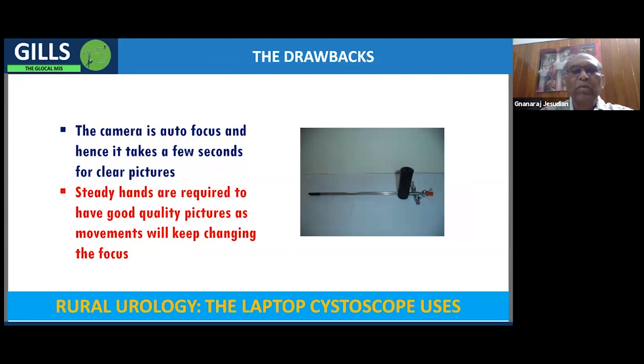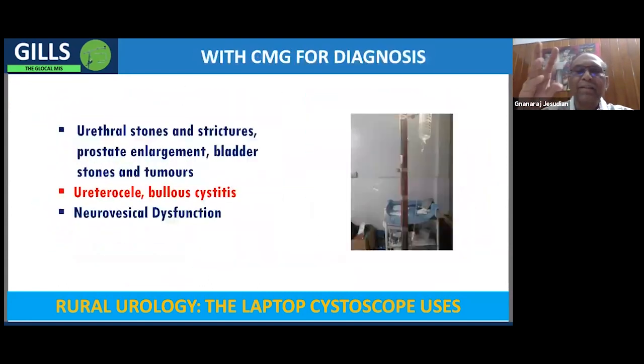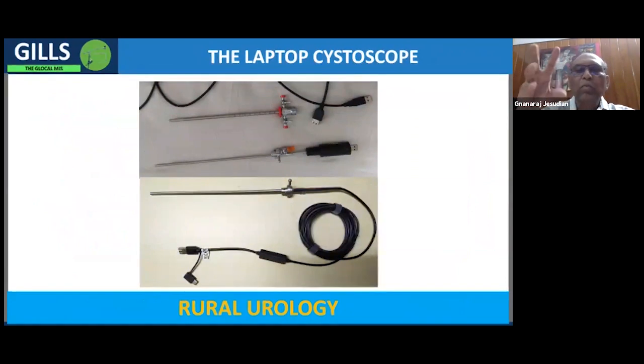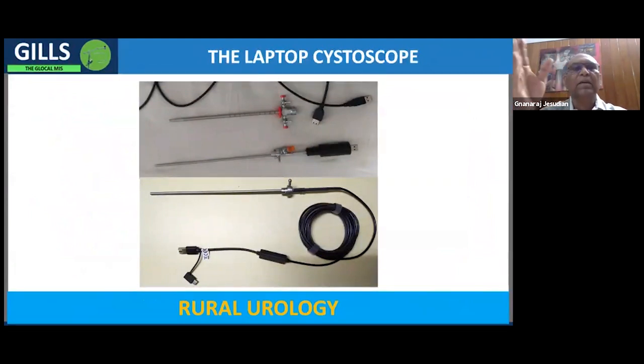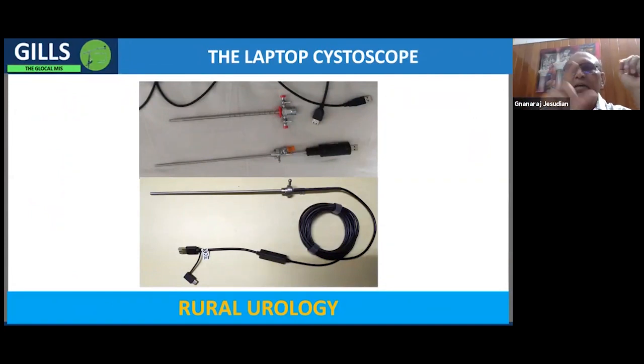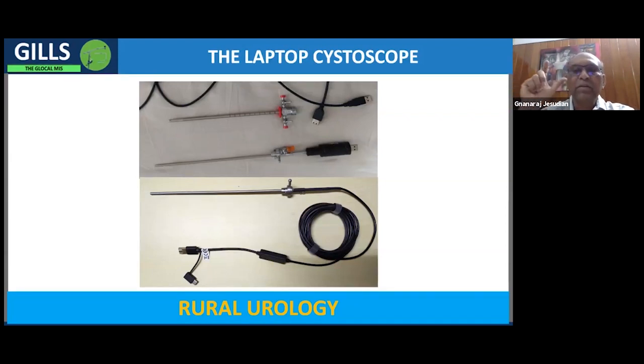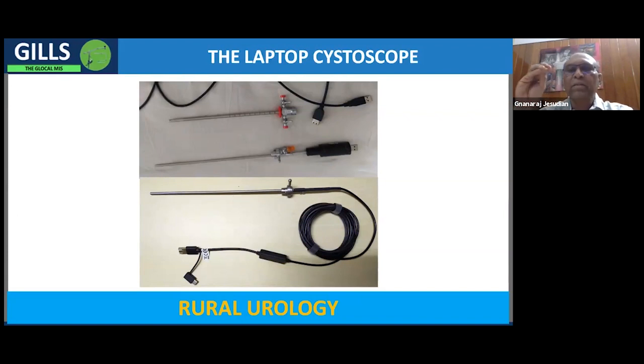This scope, what we are seeing here is the first generation one. The first slide will show the second and third generation scopes that we have made. So what are the disadvantages of these scopes? Here what we have done is we replace the telescope with the endoscopic camera. This dramatically reduces the cost because the telescope is the most expensive part of this entire system.